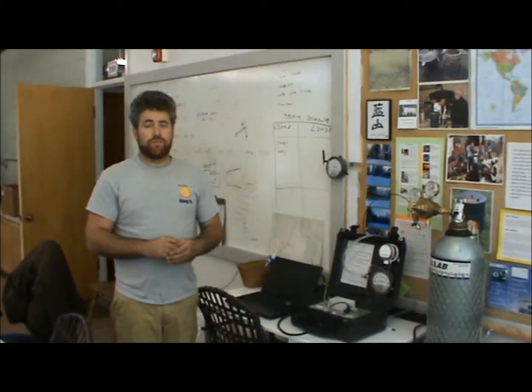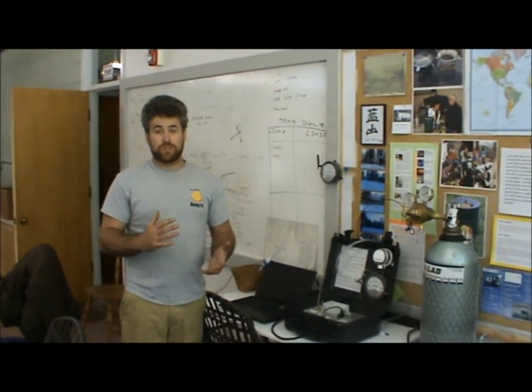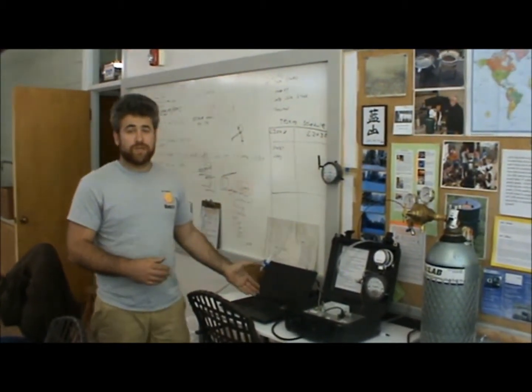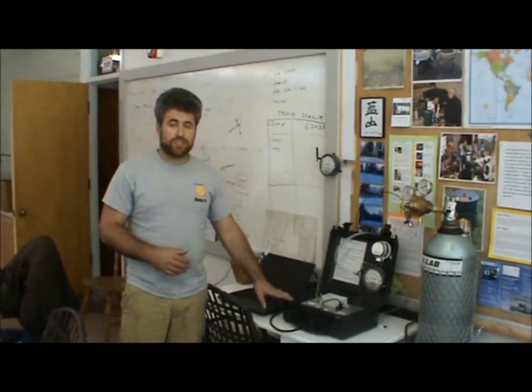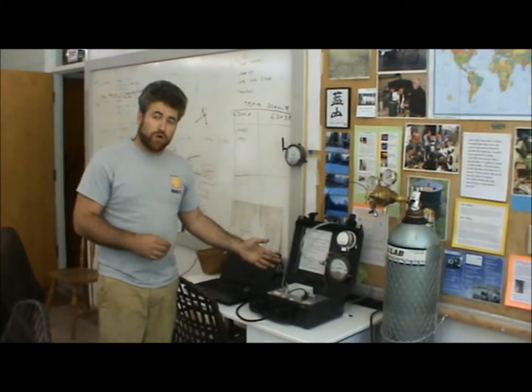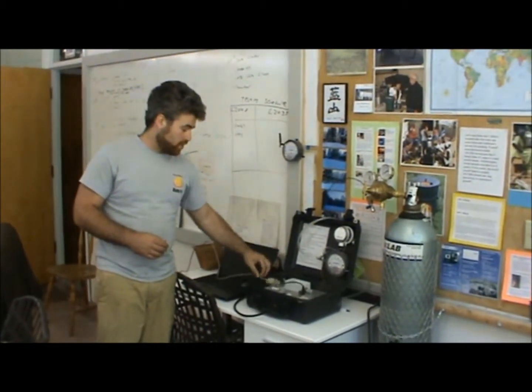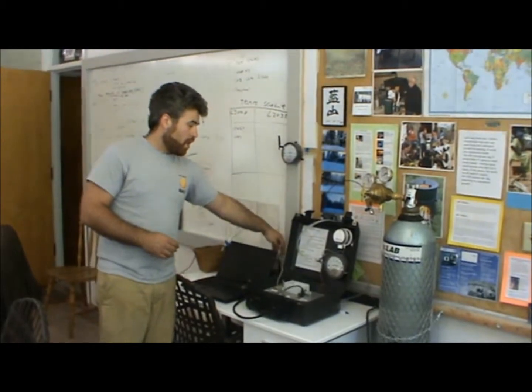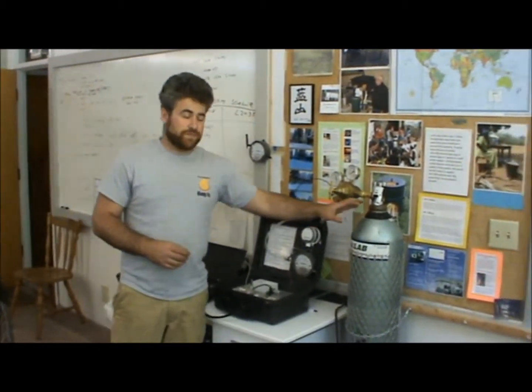For the carbon monoxide calibration, you're going to need some tools. One is your computer. The same computer you use to run tests is fine. Your sensor box, obviously, along with its power cord and the computer data cord connecting it to its computer. You'll need your tank of gas. This tank of gas has 300 ppm carbon monoxide and 3000 ppm carbon dioxide. The balance, the rest of it, is air. It's important to get a balance of air and not just nitrogen or oxygen, because for the calibration process and the sensors it has to have that balance.